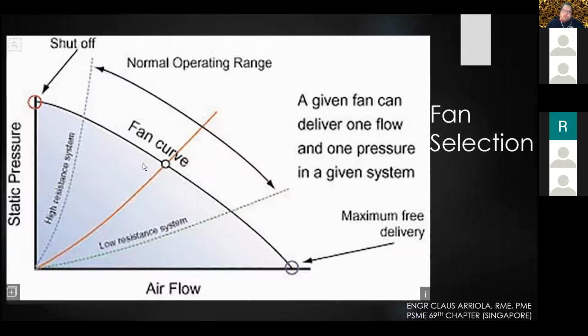Normally we don't want to size or select your fan outside the fan curve. Normally you want to put extra space, so your duty point is around here. That's the best selection. At least you have space to upgrade or expand your impeller.